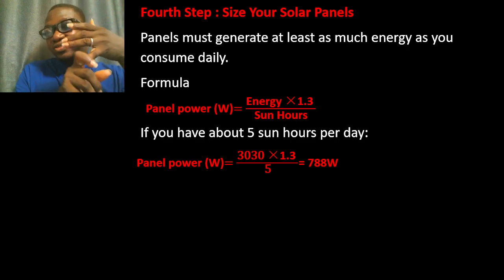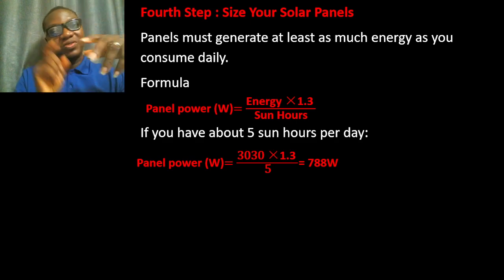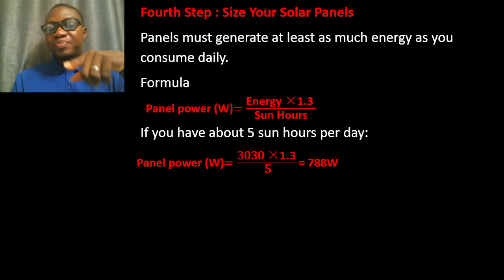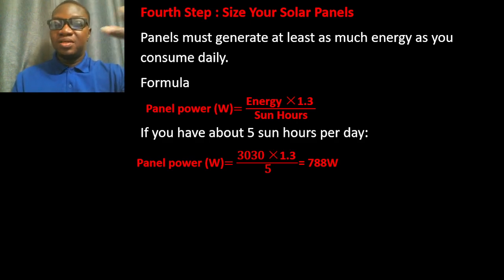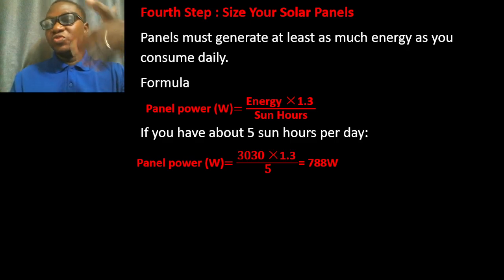In that calculation, there is no loss, no weather problem, no over temperature, nothing. So that is an ideal situation, and that is different from reality. So in solar engineering, you add some tolerance to it. That is a normal rule of thumb. You use at least around 1.25 to 1.5 to multiply it.